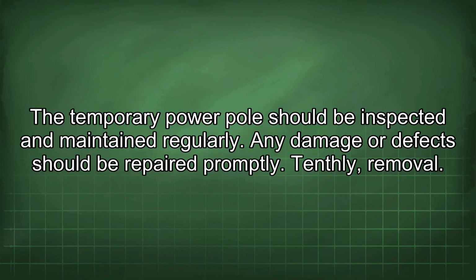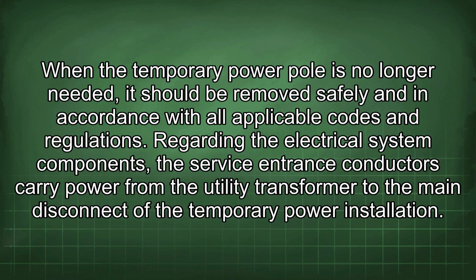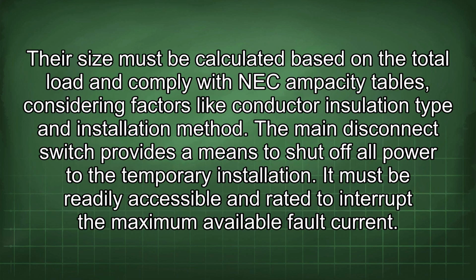Tenthly, removal. When the temporary power pole is no longer needed, it should be removed safely and in accordance with all applicable codes and regulations. Regarding the electrical system components, the service entrance conductors carry power from the utility transformer to the main disconnect of the temporary power installation. Their size must be calculated based on the total load and comply with NEC ampacity tables, considering factors like conductor, insulation type, and installation method.